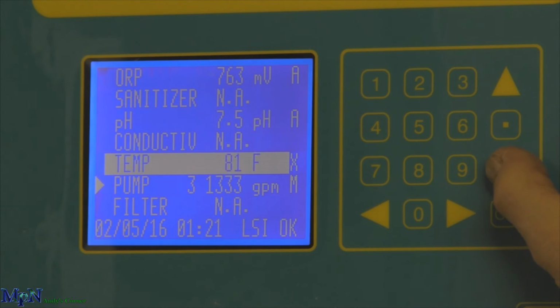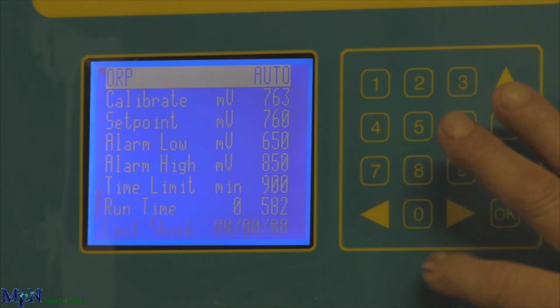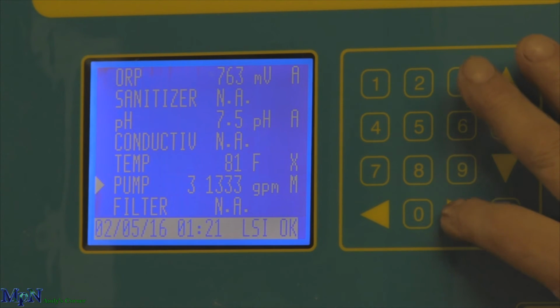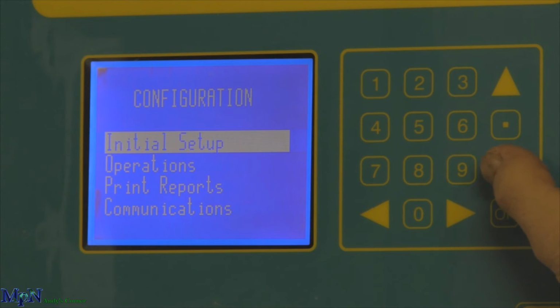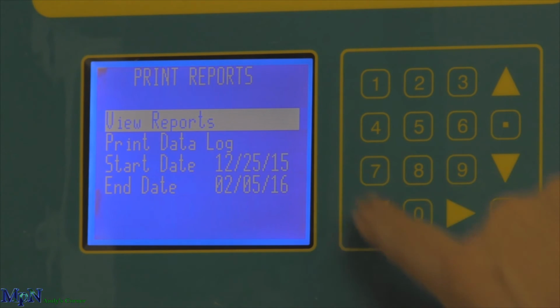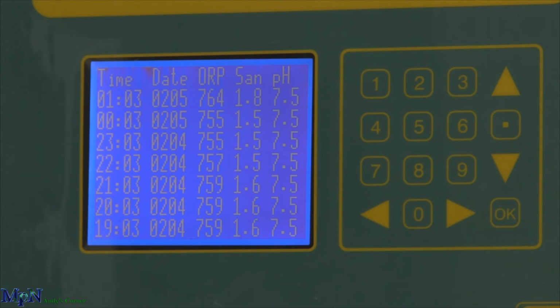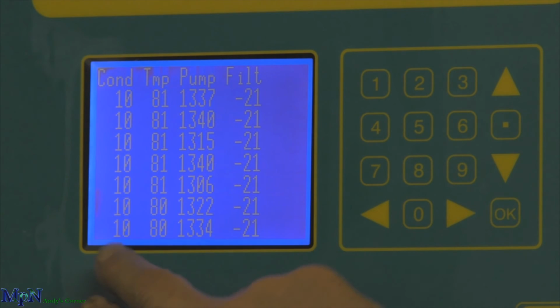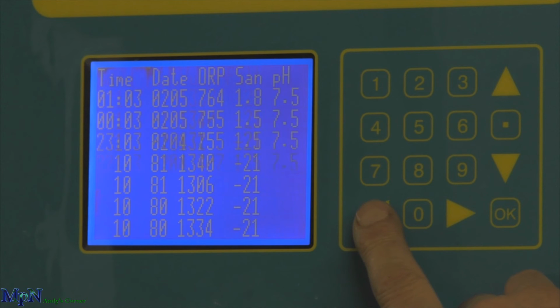Another thing this unit does is, every hour, it will store the readings that are on the unit. We'll go down to view reports. If you're on a ChemCom or the Ethernet, you can pull this up at your desk and print them off a printer. This tells us the date, the time, ORP reading, the sanitizer, which is a kind of calculated value, and our pH, which right now is 7.5. We'll right arrow over, and if you had pressure transducers on your system, it would tell your pressure reading. It tells how many gallons per minute we're running right now. You can print that once a month and put it into a file so you know what happens every month. To get out of that, we'll just left arrow back out.